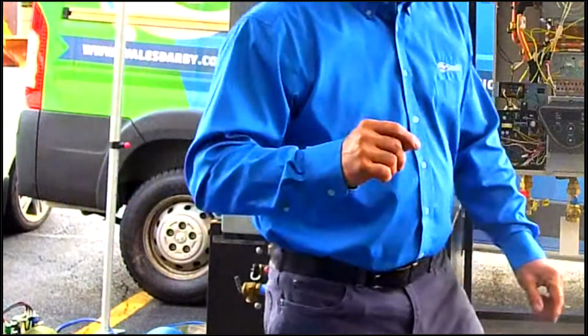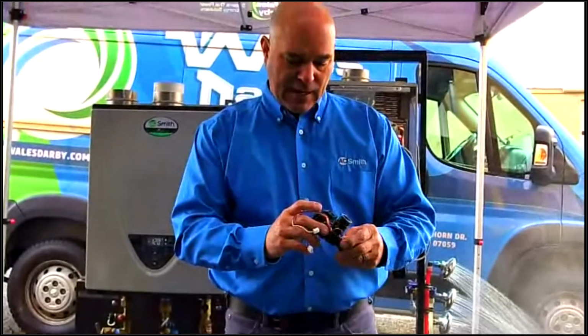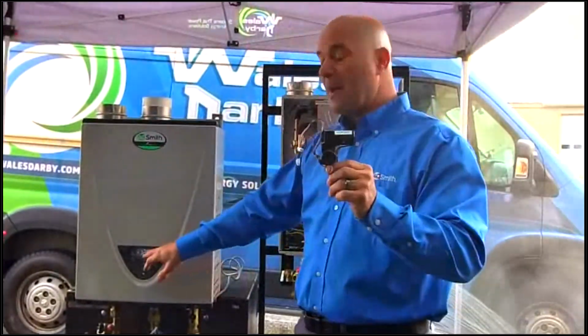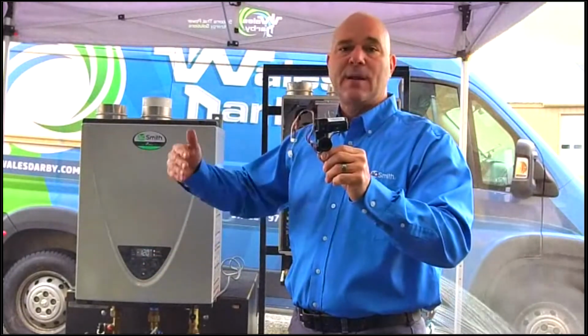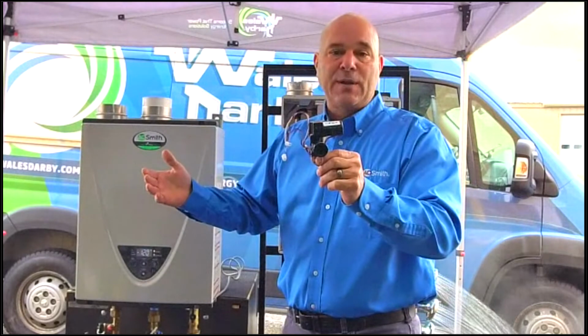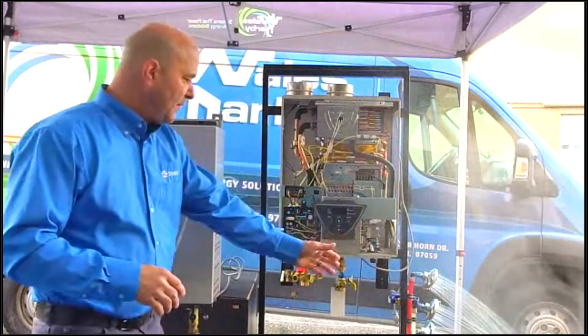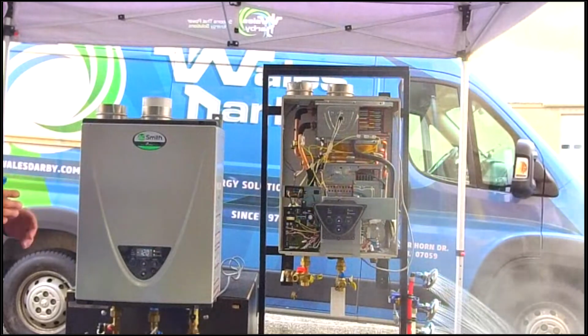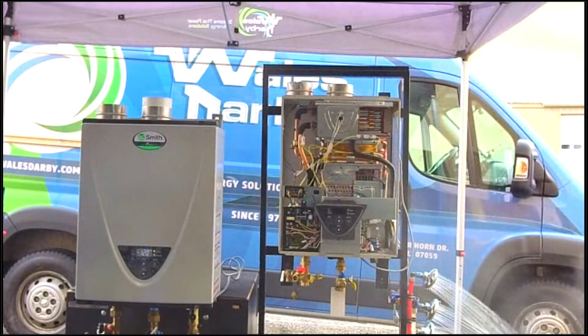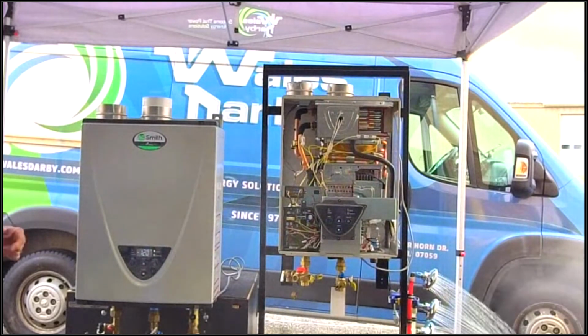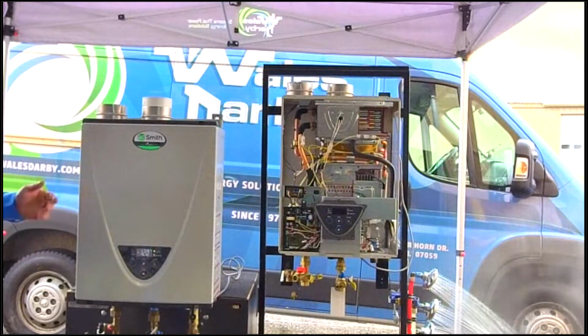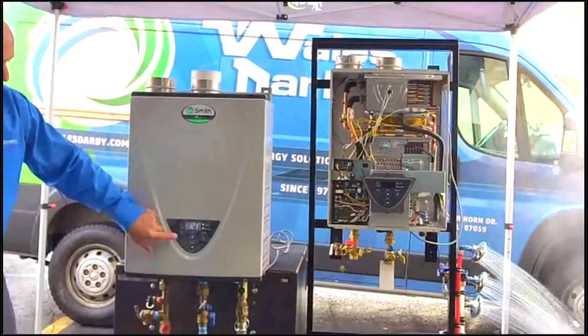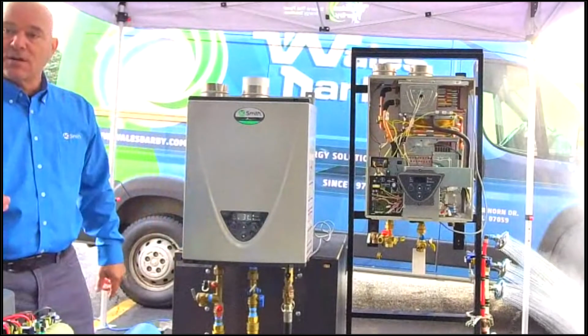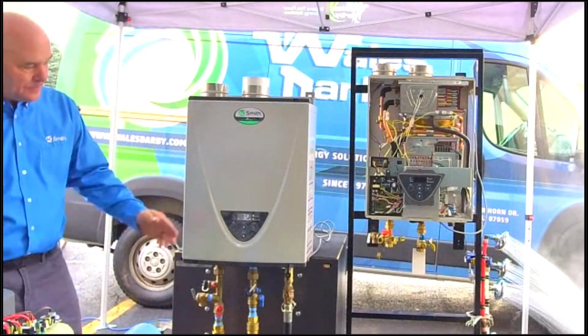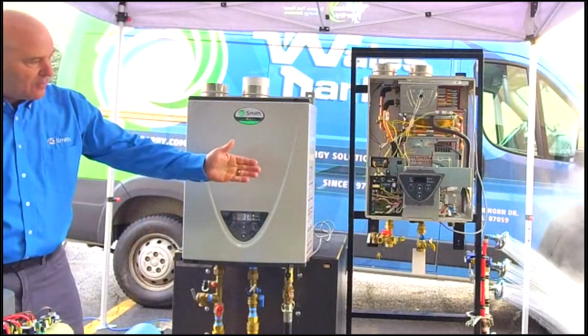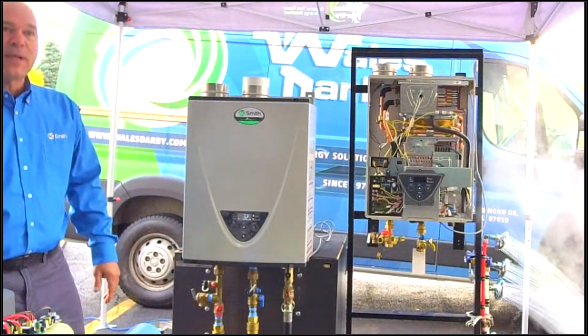Yeah. Remember, going back to the flow switch, if this flow switch malfunctions, I probably won't get an error code here, because if I can't recognize flow, I have no ability to give you an error code. So now that we have flow, the unit is on. You can see how quiet these are. I don't even know if you guys can hear it coming through the camera. The camera realistically is about 7 feet away from this unit, and we're running, and you can really see it condensing now. The higher the flow rates, the more water we're producing, the more it'll start to condense. So we're at 3.2 gallons a minute. You can see that's some pretty hot water running over there. Jamming out some good hot water.